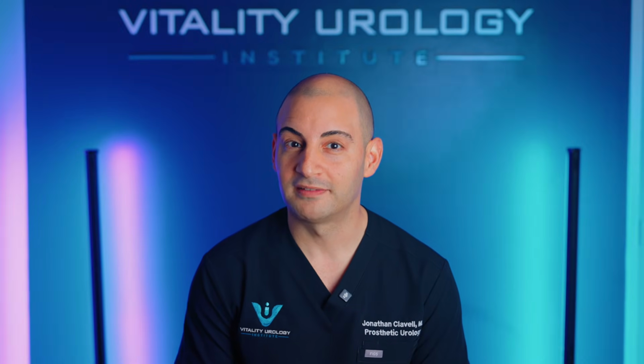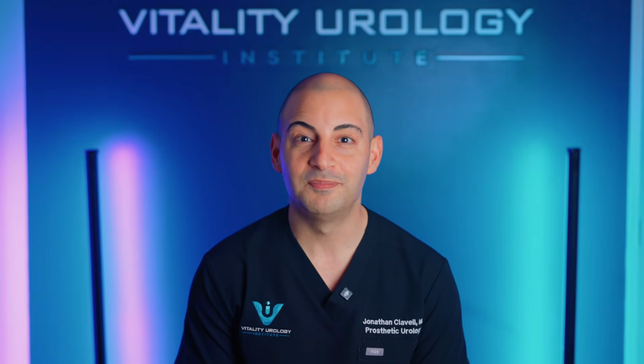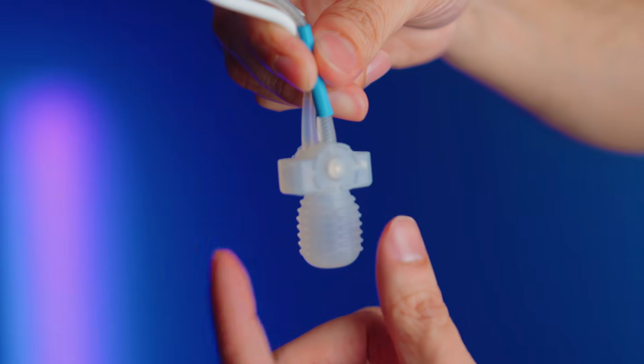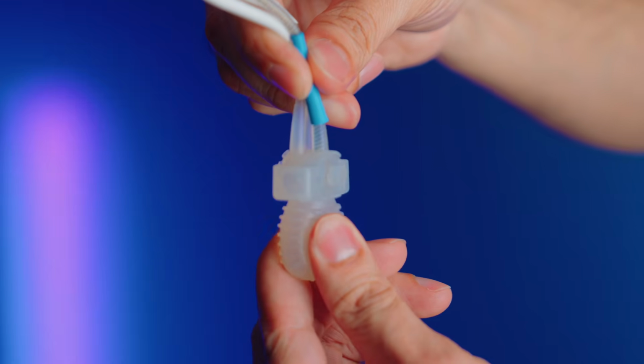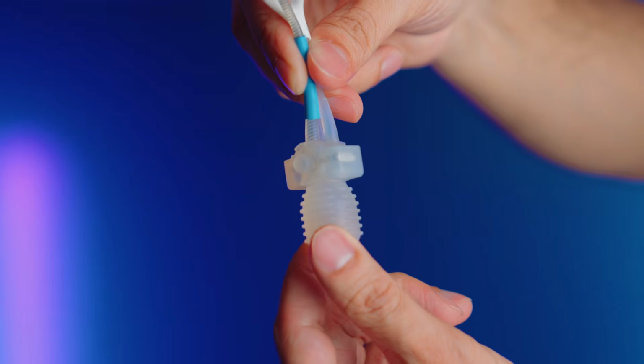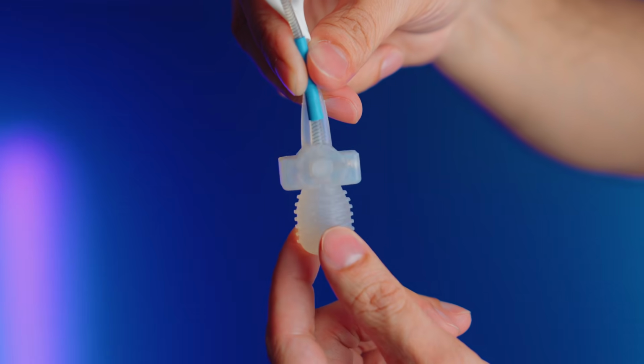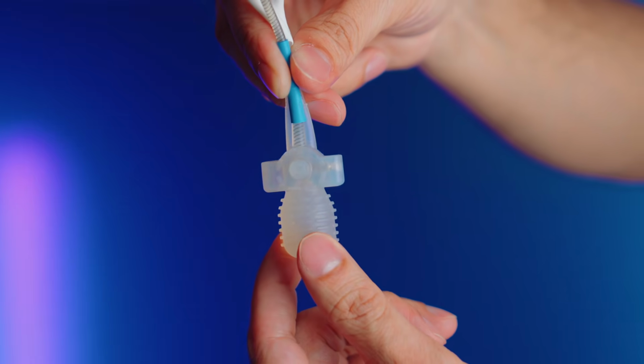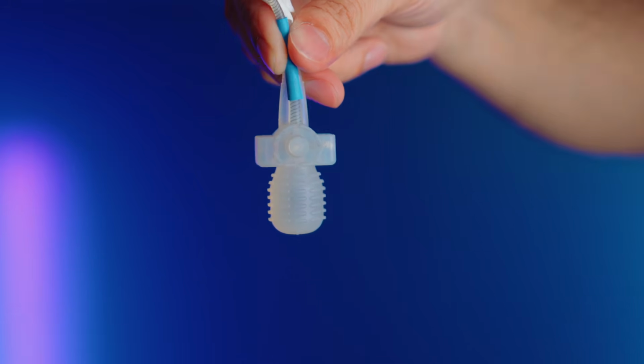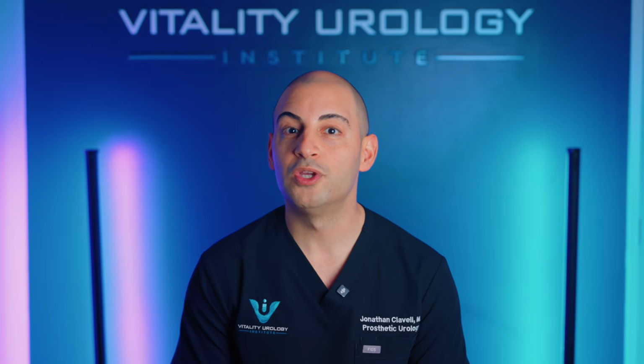The MS pump, which again stands for momentary squeeze, has been the standard pump for AMS 700 penile implants for over a decade. It's designed, as you can see, with a bulb on the bottom that you press to get the implant inflated and a small rectangular shaped mechanism on the top that contains a button in the center that you press and hold to deflate the implant. It is designed with a momentary squeeze deflation button, meaning you have to hold it down for fluid to transfer from the cylinders back into the reservoir. It also contains a lockout valve that prevents autoinflation, which is a term that we use for when the cylinders start inflating on their own without you squeezing the pump.